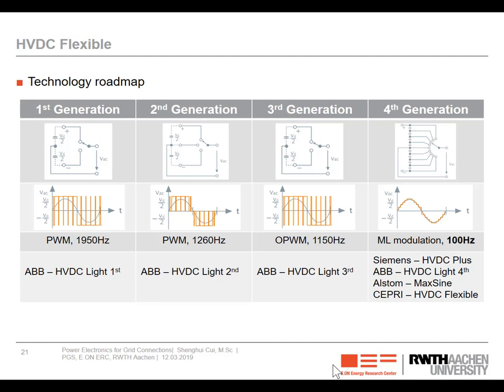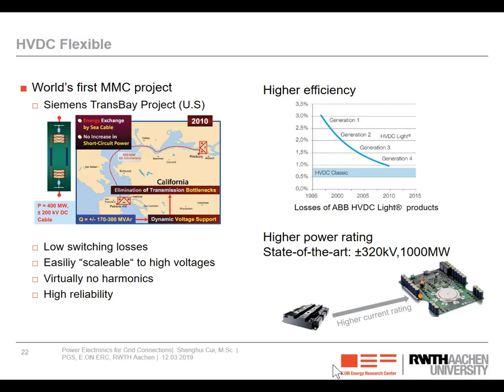18 years ago. The nice thing about this converter is that it presents almost perfect waveforms, even though it is a power electronics converter. As you can see here, different from previous technologies, the voltage quality of the converter is very, very good. In the meantime, the switching frequency of the devices can be reduced to almost 1/10, only 10% of the previous version, so that it can operate extremely efficiently. Here, I got some information from ABB. As you can see, in the first generation the loss of the converter is around 3%, but in the fourth generation products it is already below 1%, approaching the efficiency of the classical thyristor-based HVDC.